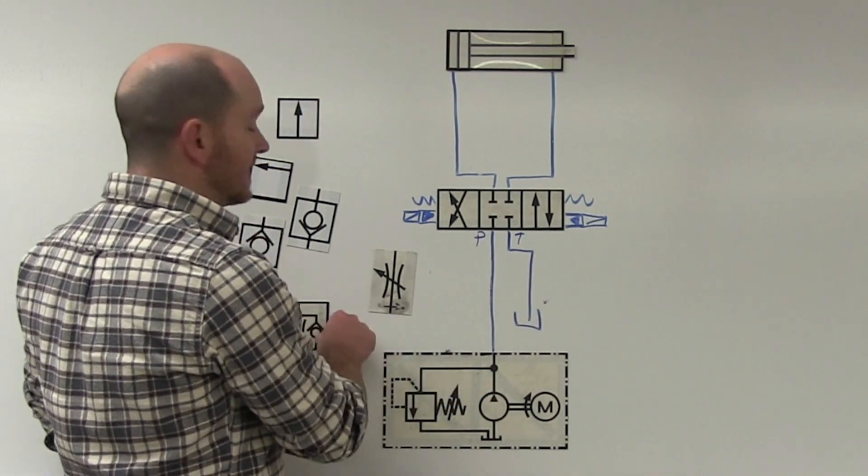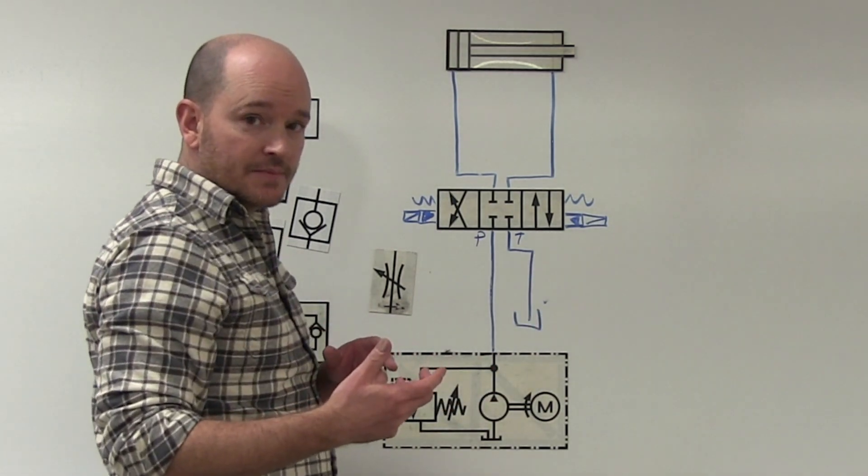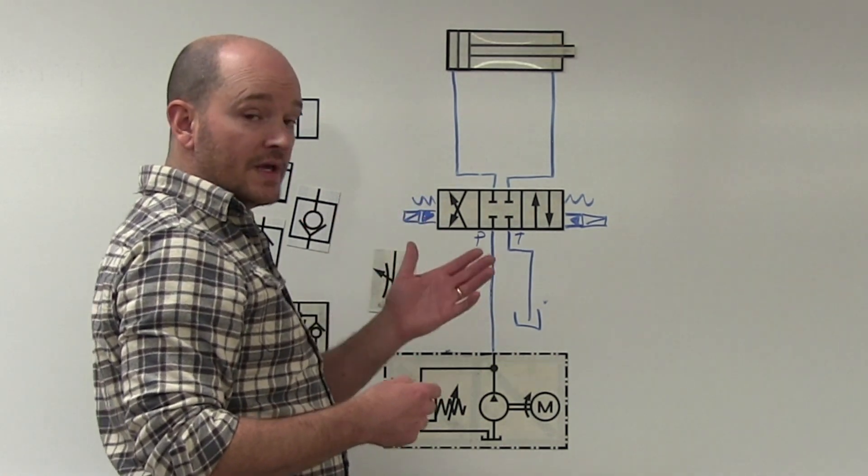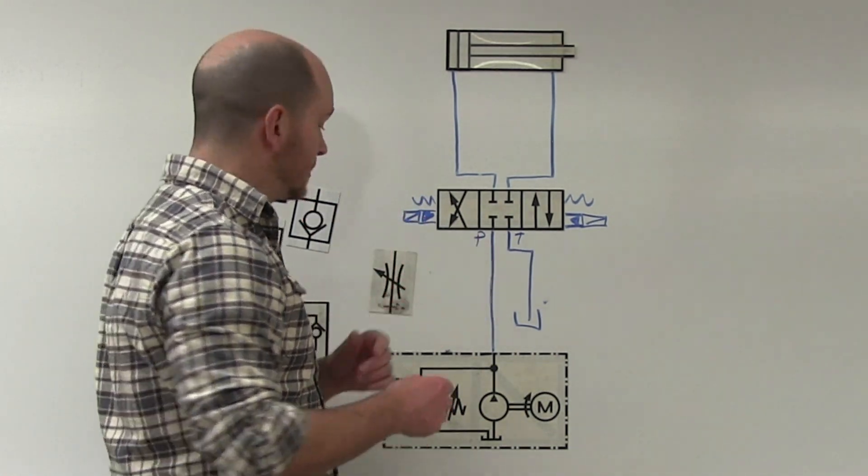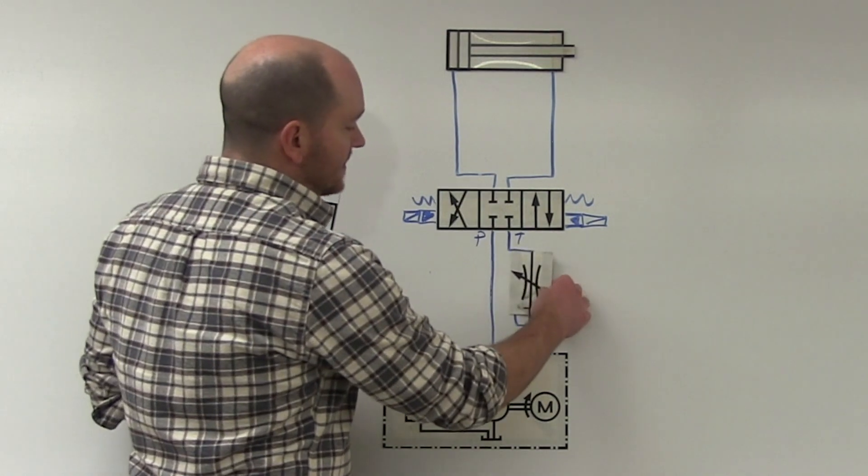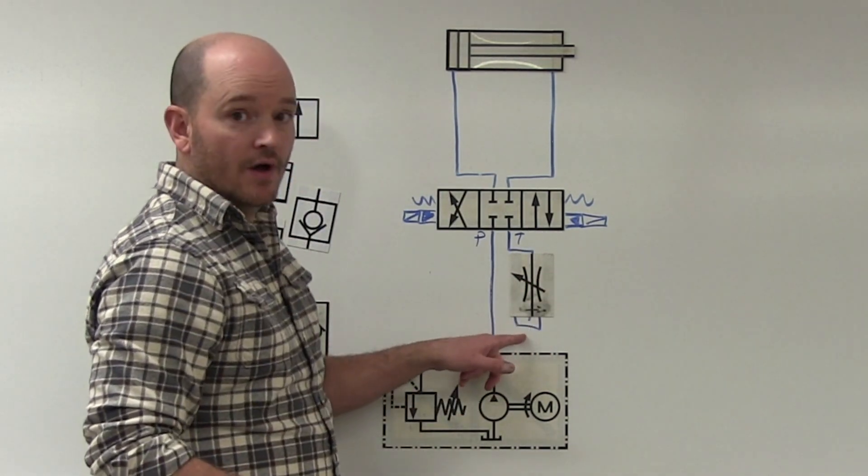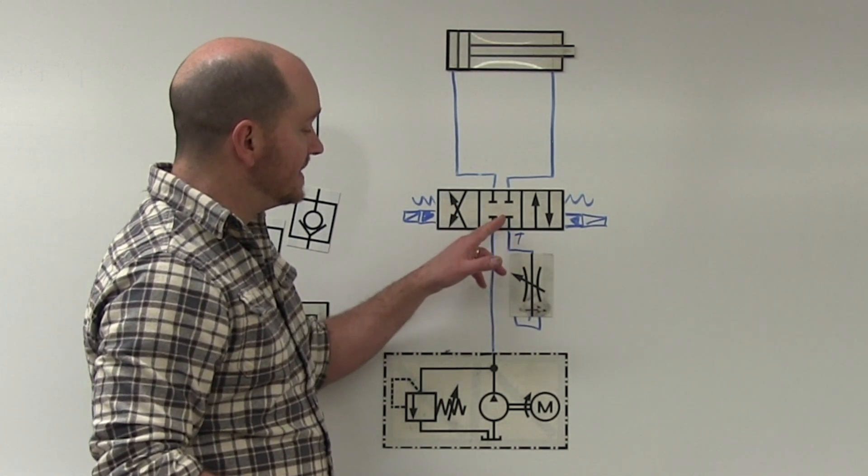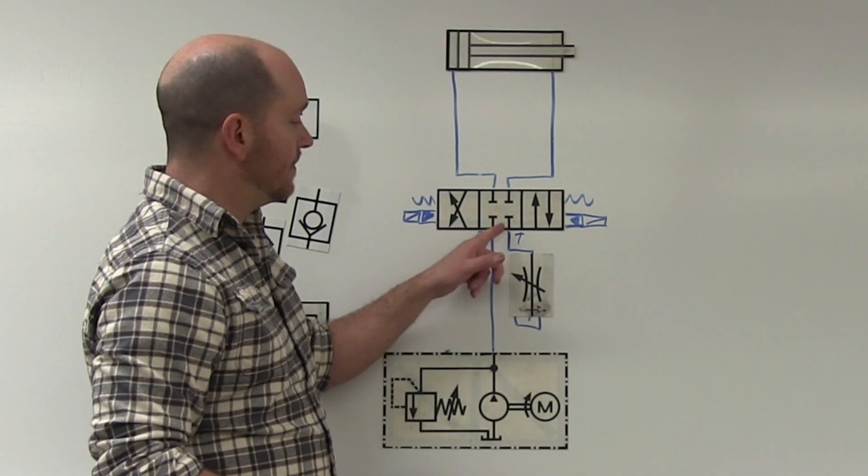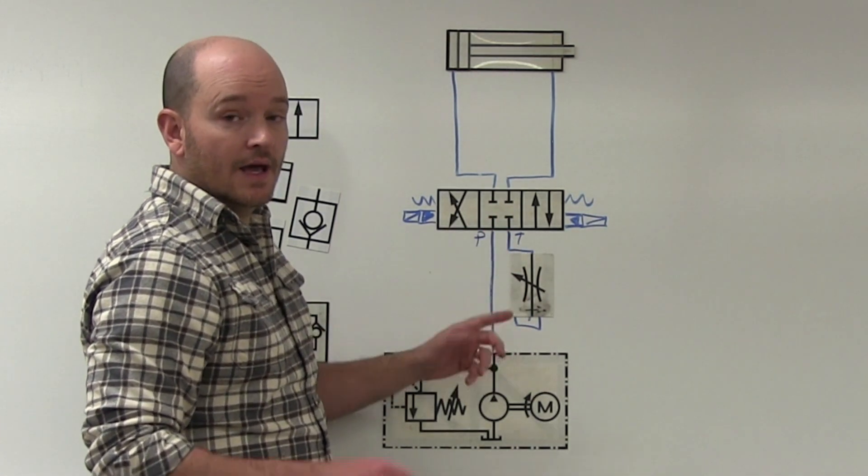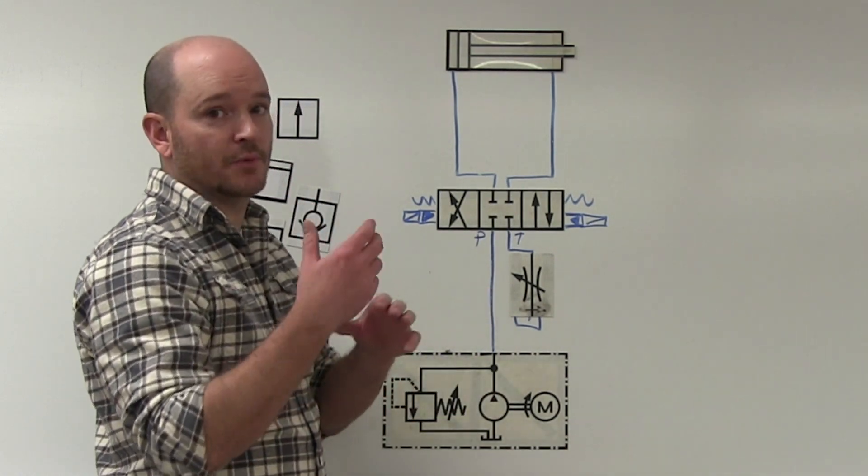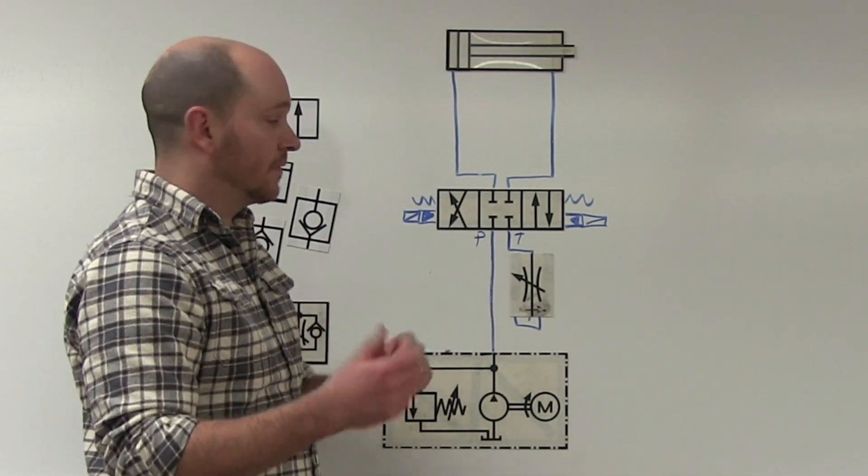This is something that you see with single acting cylinders sometimes, that are using like a 3-2 directional control valve. People will sometimes meter those out by placing a needle valve between the tank port down to the tank. And that can save money, sometimes it's more convenient for installations. There's a number of reasons for that.